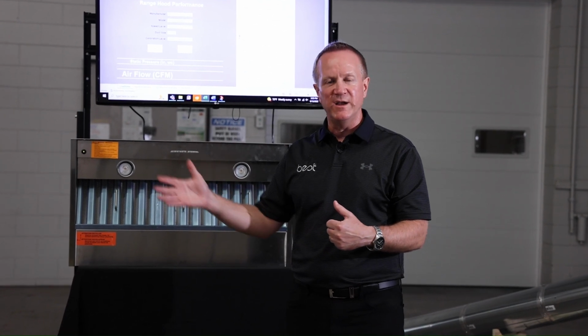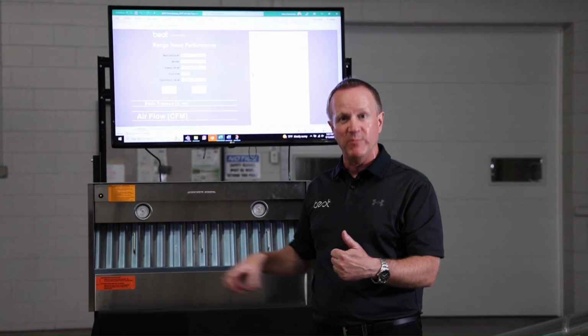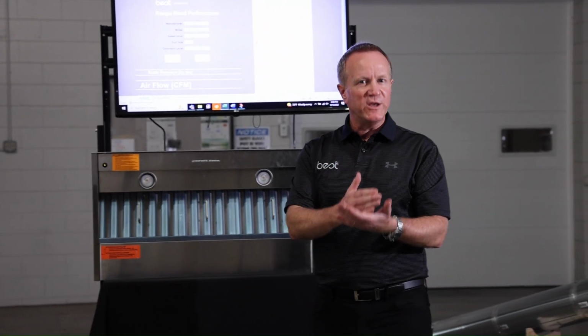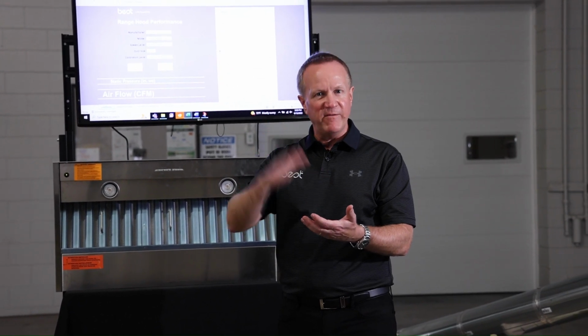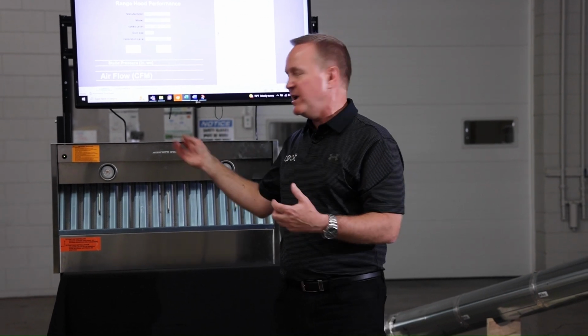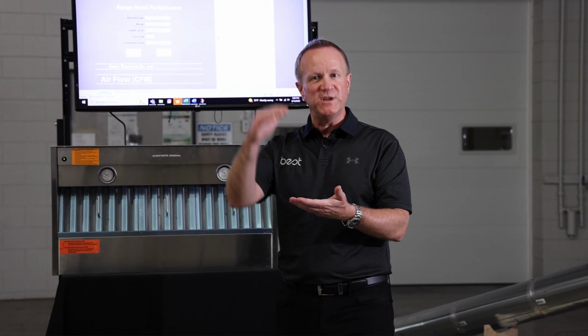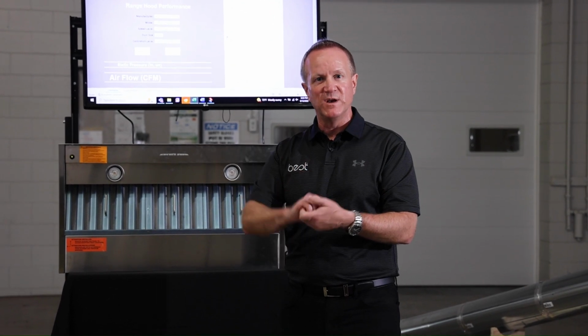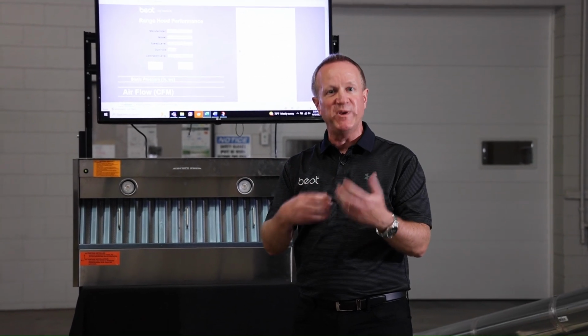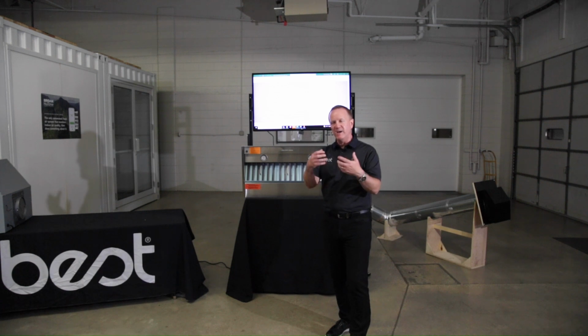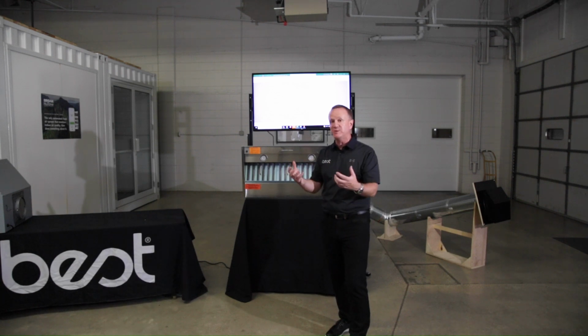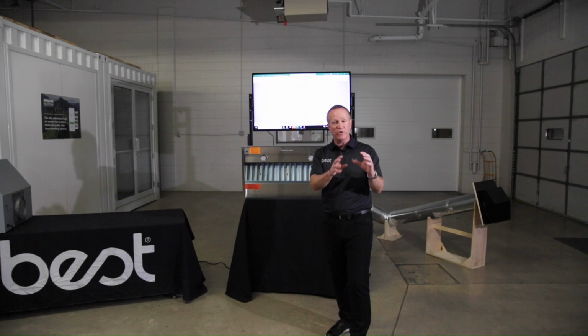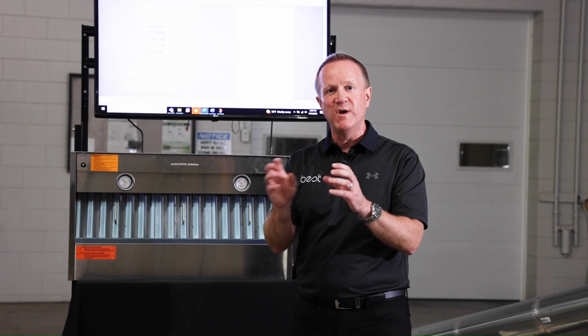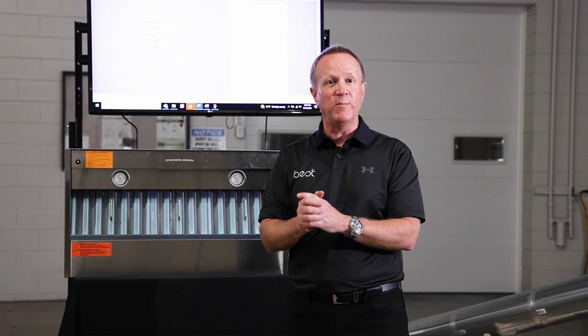So what's actually going on here is the hood is measuring the amount of back pressure that's being generated. The IQ6 and the IQ12 each have 11 different electronic profiles that are communicated between the control board and the blower itself that allows it to perform at a little bit higher level of performance. So what the hood is going to do is run at each of the speeds for a period of time. And it's going to verify that it needs profile 3 or profile 8. And it's going to measure the back pressure at medium speed, at high speed, at burst. And it's going to lock in that performance that is going to allow an IQ6 to perform at or as close to 600 as possible. It's going to allow that IQ12 to perform at or as close to 1200 CFM as possible.